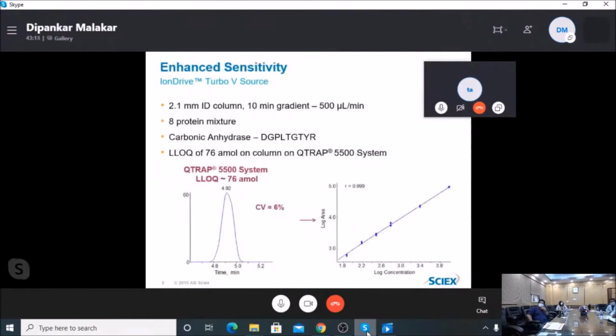This is one example where the ion drive Turbo V source in the 5500, the lower version instrument, we can detect at the attomole level, like 76 attomole, with a very low percentage CV, around 6%, and get a good quantitation curve, calibration graph, with the 8 protein mixture.